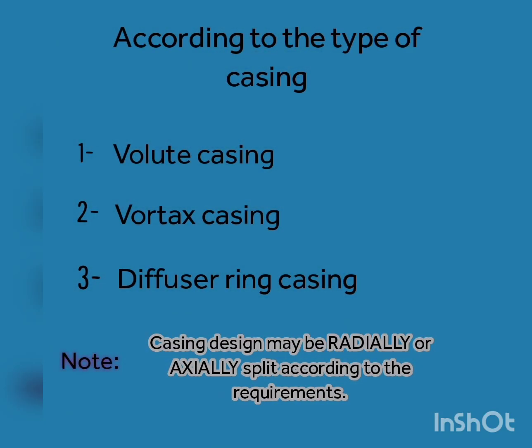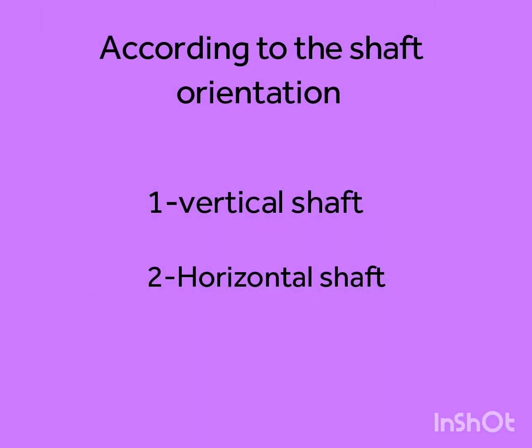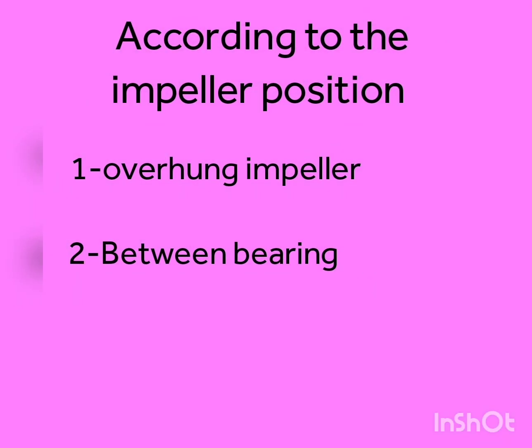According to the type of casing — volute casing, vortex casing, diffuser ring casing. Note: casing design may be radially or axially split according to requirements. According to shaft orientation — vertical shaft, horizontal shaft. According to impeller position — overhung impeller and between bearings.